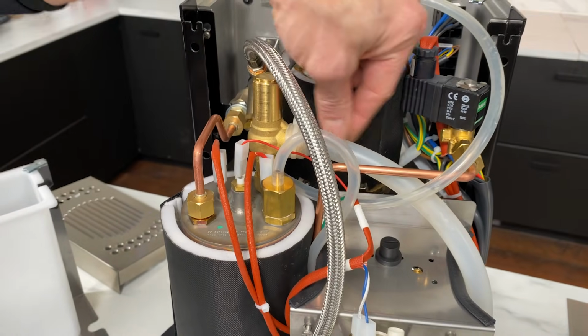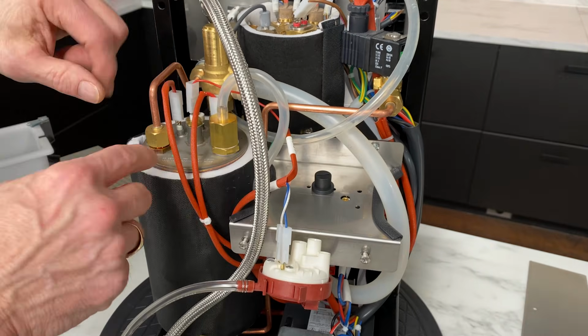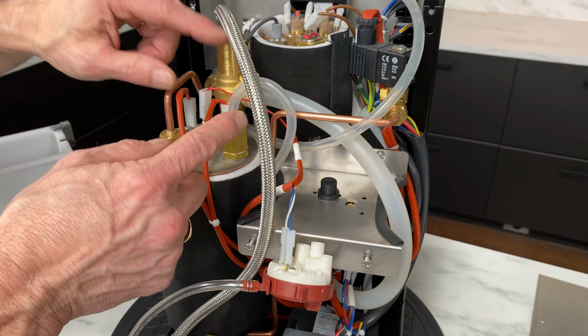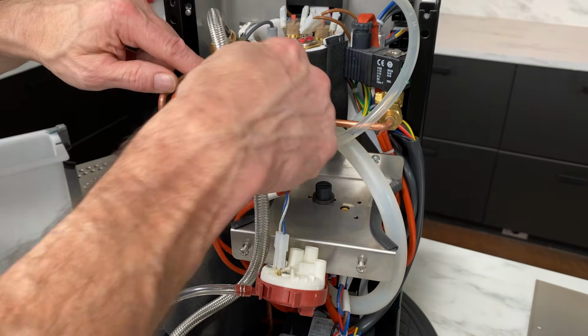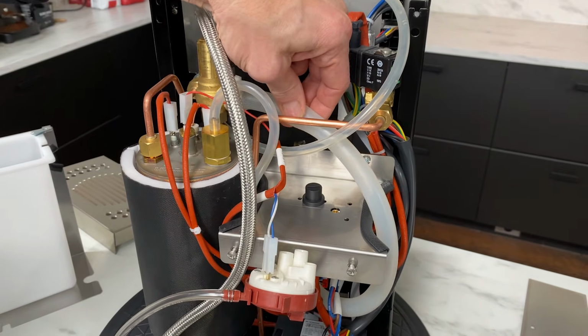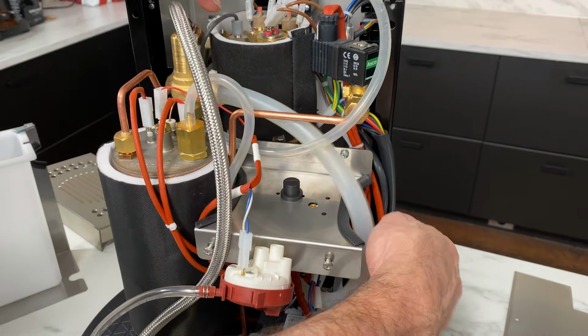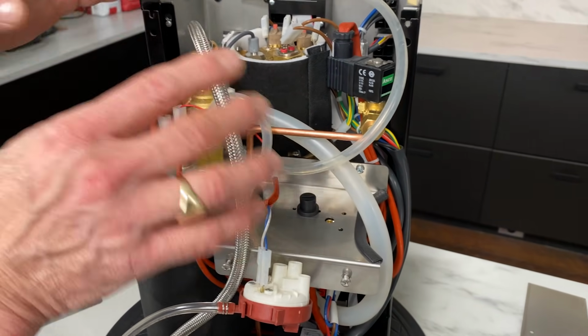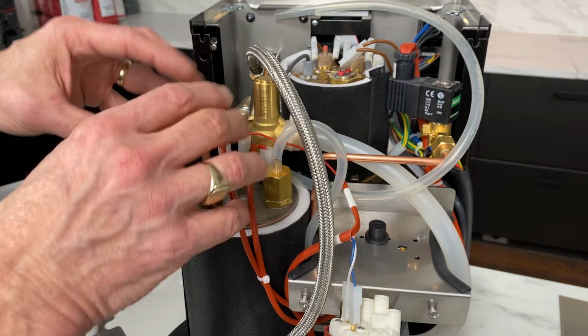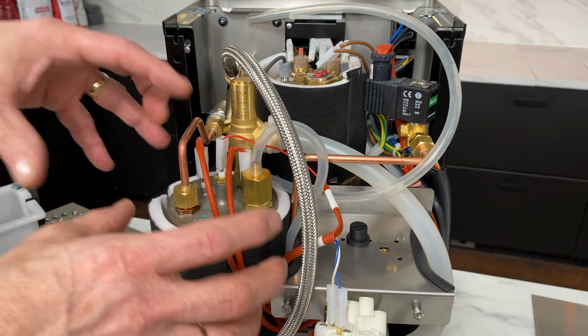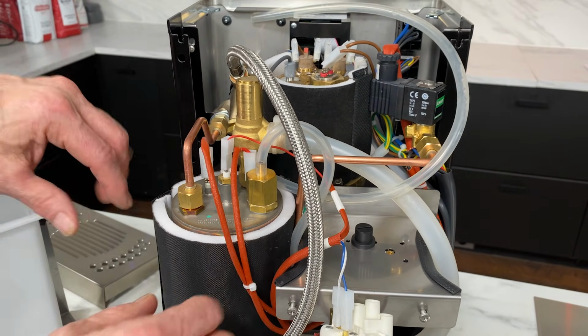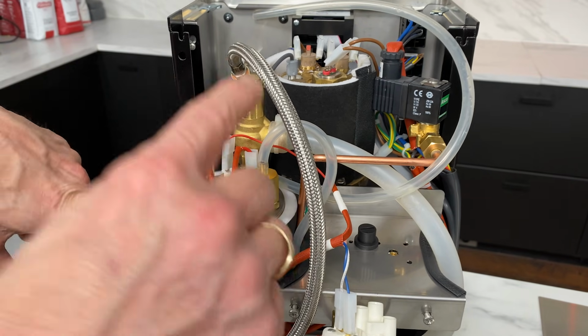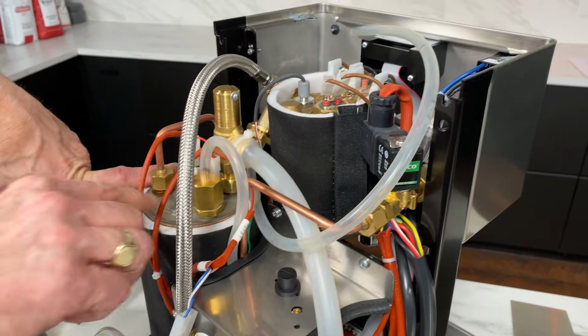Yep, it's got this big tube here. So if the pressure in this boiler exceeds 1.9 bar, this valve opens and releases pressure. That's why we've got a really big tube. This tube also goes out to the drip tray. Now, it's very rare for that to happen. It's just for safety. If the pressure builds up too much in that boiler, bad things could happen. So that is the service boiler for your steam and your hot water.